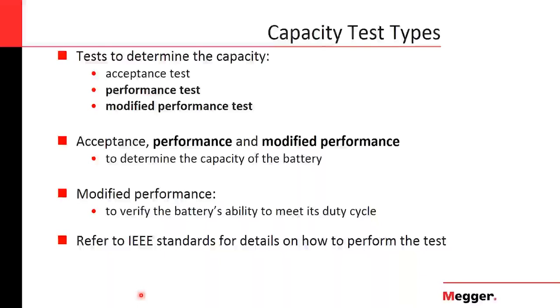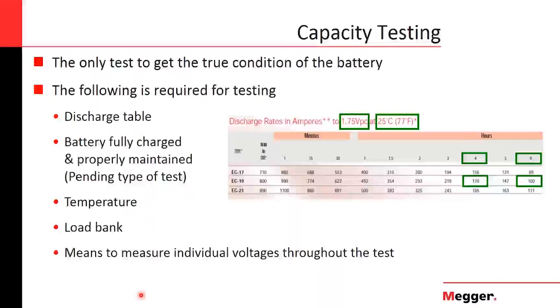One thing about capacity testing is that it is the only test that can get you the true condition of the battery. Impedance testing, or ohmic values, will give you a very good indication of the health of the battery, but it will never tell you the capacity value of the battery. So the discharge test, or capacity testing, is the only one that can give you the true condition. And it's probably an overall indication of the string, not of each cell. That is the advantage of the ohmic measurement, that it can tell you the condition of each cell.